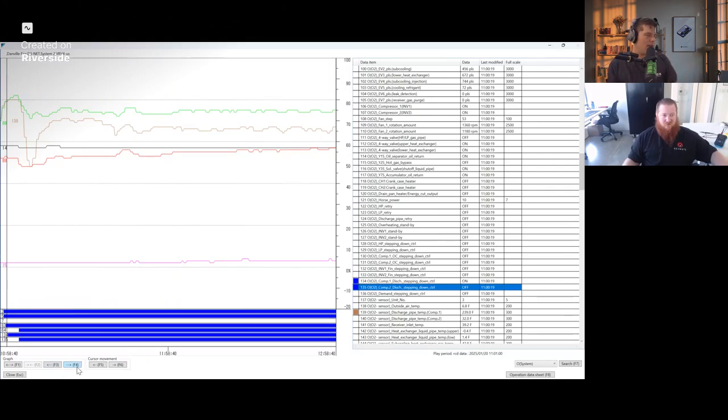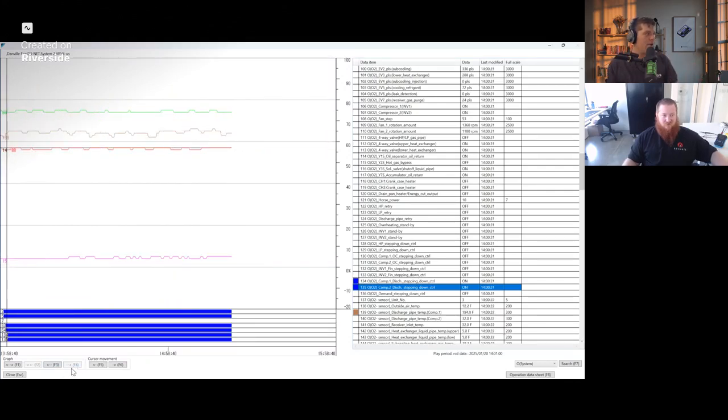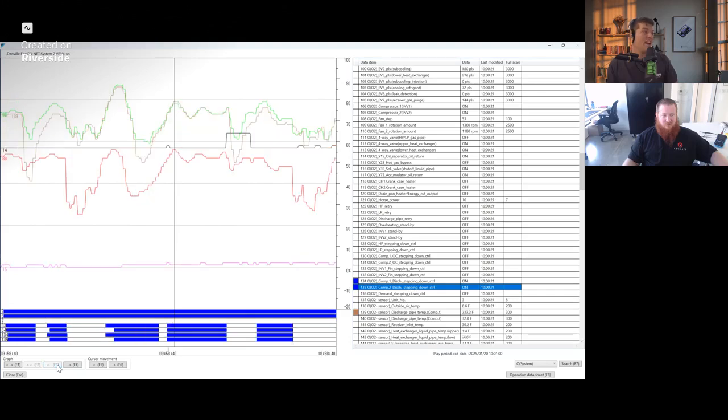Because remember, we're looking at 2 hours worth of data here in one viewpoint, and it just never comes out of it. So you can see where it starts up the system, and this is normal, right? When you say that's normal, Donald, when a system restarts, when you put service checker on and you populate the update map, it's normal for it to get a little wonky the first 15, 20, 30 minutes to settle out. Yeah, once it goes to restart standby, it's got to start over again, right?